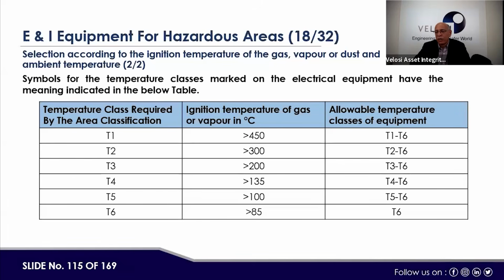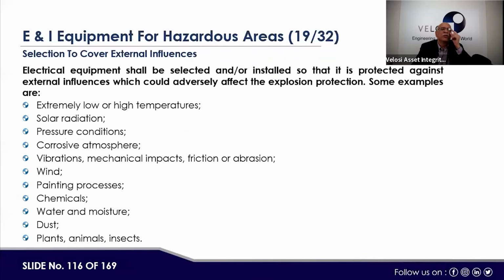It is also applicable to the surface of the engine chamber, or any hot surface in that area, which should not create a temperature more than this class, which is defined by the applicable HAC class. Now, electrical equipment shall be selected and or installed so that it is protected against external influences which could adversely affect the explosion protection. For example, extremely low or high temperature, solar radiation, pressure condition, corrosive atmosphere, vibration, mechanical impact, friction or abrasion, wind, painting process, chemical, water and moisture, dust, plants, animals, and insects. So we have to consider all those, so that the protection class and the equipment temperature bearing capacity are not affected by the external factors.